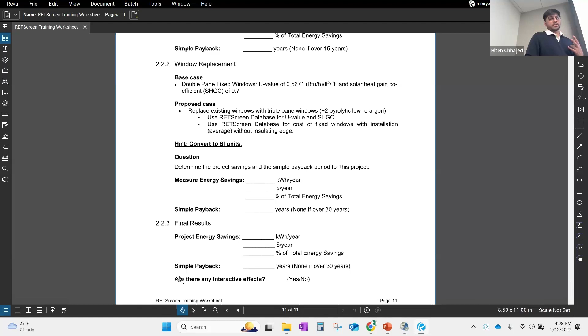If I were to insulate this particular room and make it tighter, with more insulation in the walls, there's less leakage, so the amount of heating and cooling you need is lower. Now, when I'm replacing those lights along with insulating the walls, LED typically gives out less heat than a fluorescent T8 would. So when you replace your fluorescent with LEDs, you save on electricity, but you increase your heating demand in the room because there's less heat emitted from the light itself. It still makes sense to replace it because the electricity savings is high enough, but both of these measures interact with each other, and the savings might not simply add up.